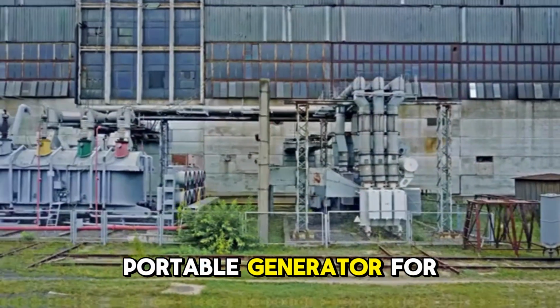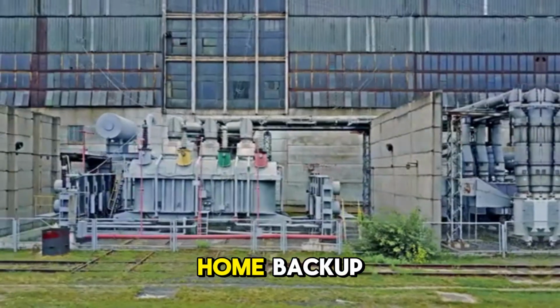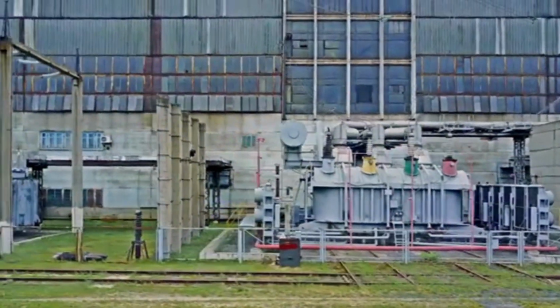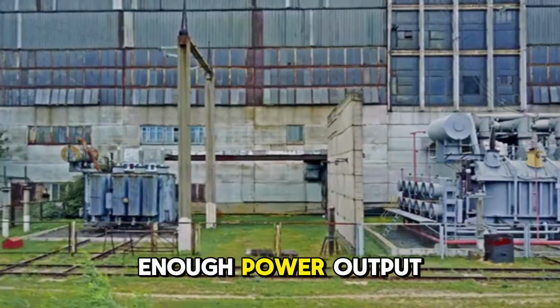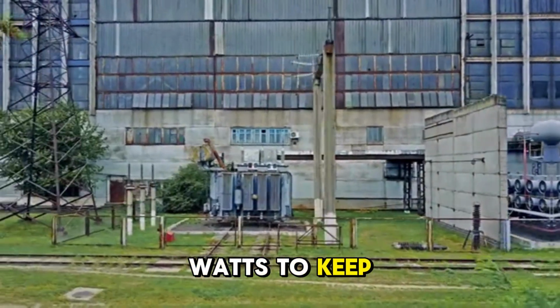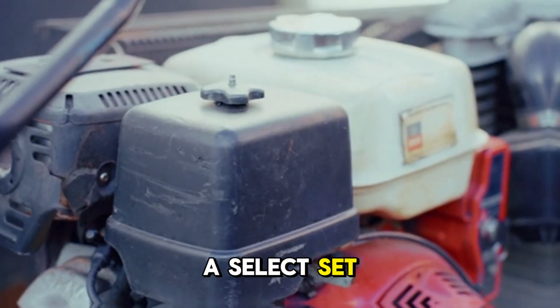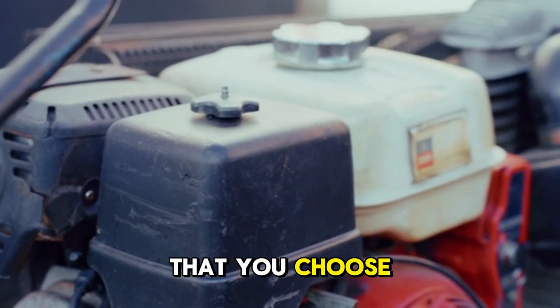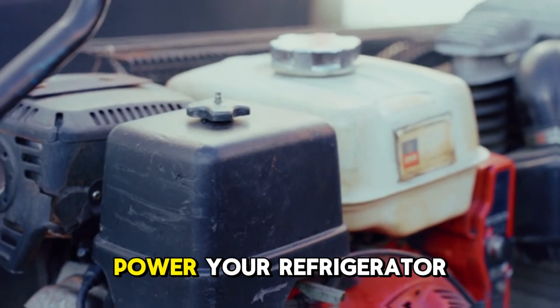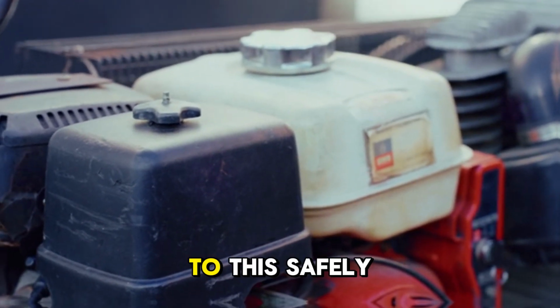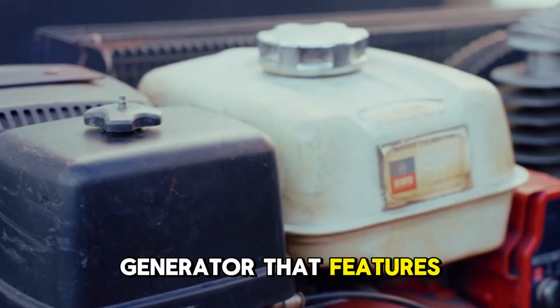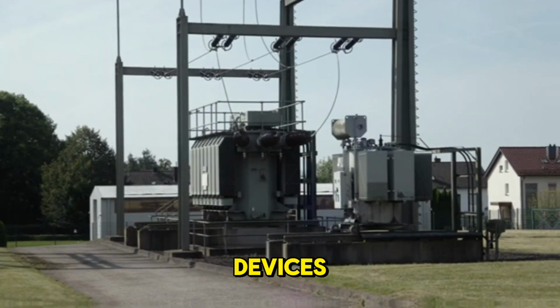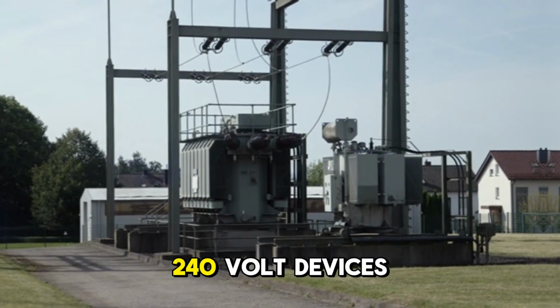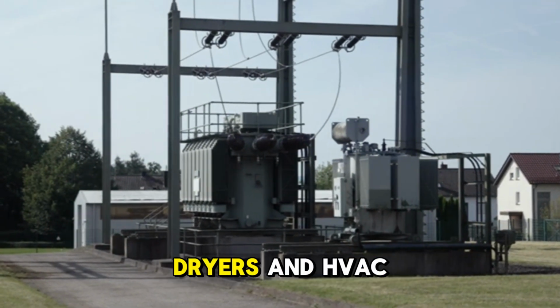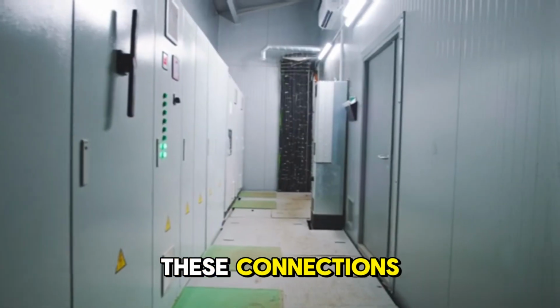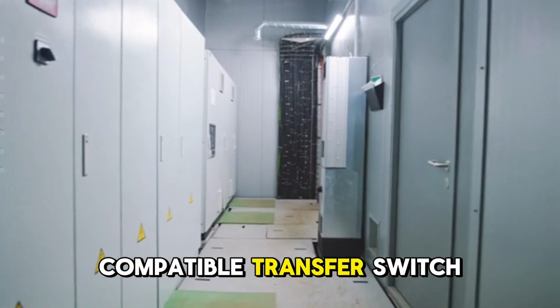Portable generator. For a portable generator to make sense as a true home backup, it needs to meet a few requirements. For starters, it must be able to produce enough power output, both starting and running watts, to keep your home electrical system running, or at least a select set of essential devices that are connected to the circuits you choose to back up, e.g., ones that power your refrigerator or well pump. To do this safely and properly, you need a generator that features a 30-amp circuit to power most 120-volt devices, or a 50-amp connection if you're powering 240-volt devices like electric ranges, dryers, and HVAC systems. These connections must then be paired with a compatible transfer switch.